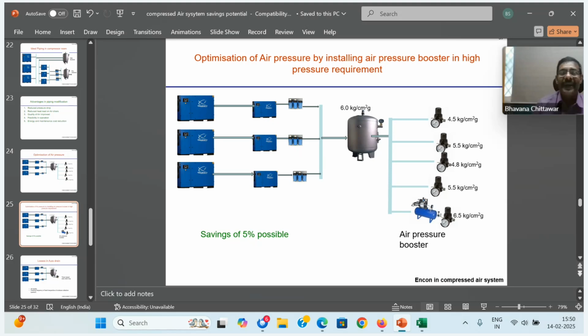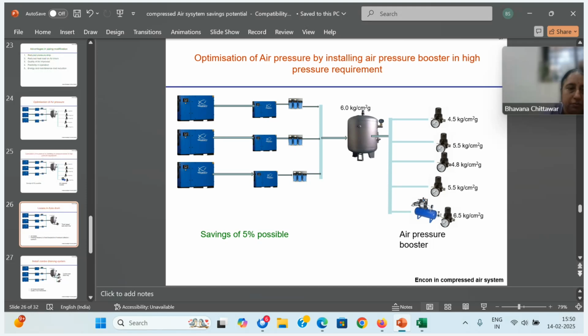Another proposal is, sometimes you cannot reduce the pressure because some applications require high pressure. Just study the application. What is the quantum of air required? If it is less than 10 or 15%, you put an air booster for that application alone. The air booster increases the pressure to the required pressure. Overall, you can reduce.